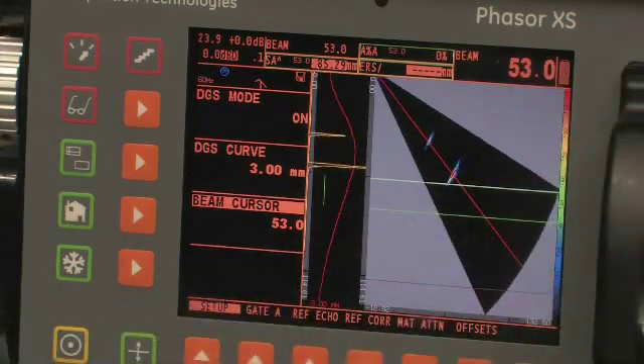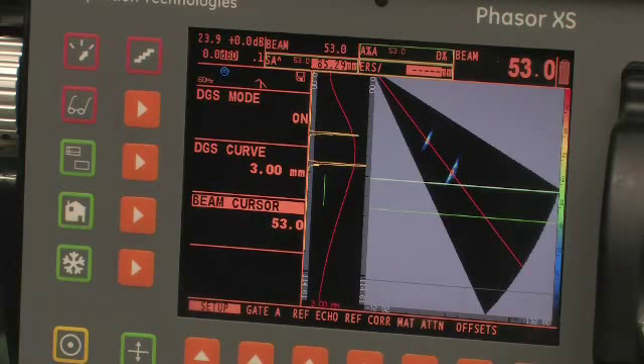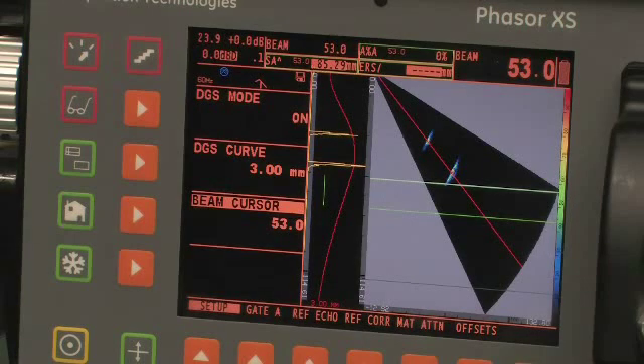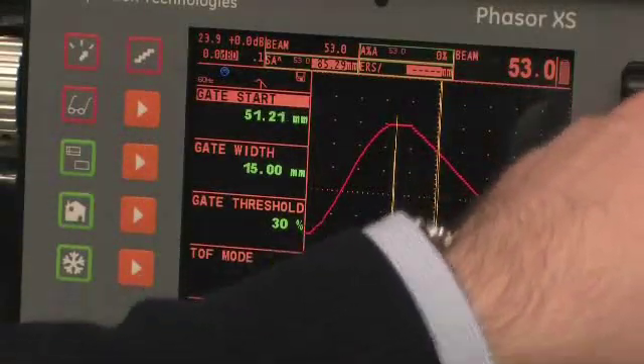When you have found the angle producing the highest amplitude, please ensure that the gate is over the flaw signal. Once the gate is set correctly, the DGS measurement is performed in a manner nearly identical to conventional flaw detectors. The end result is that the ERS is displayed on the phaser screen. It is also possible to switch the phaser back to the A-scan screen, which may enhance your ability to optimize the signals and further improve the DGS sizing accuracy.